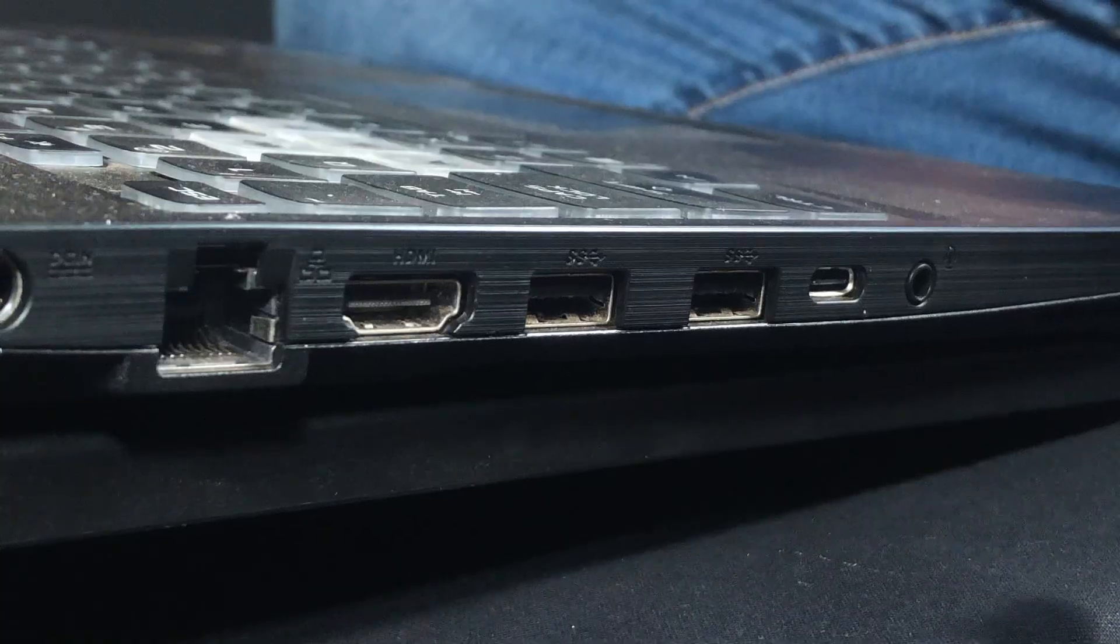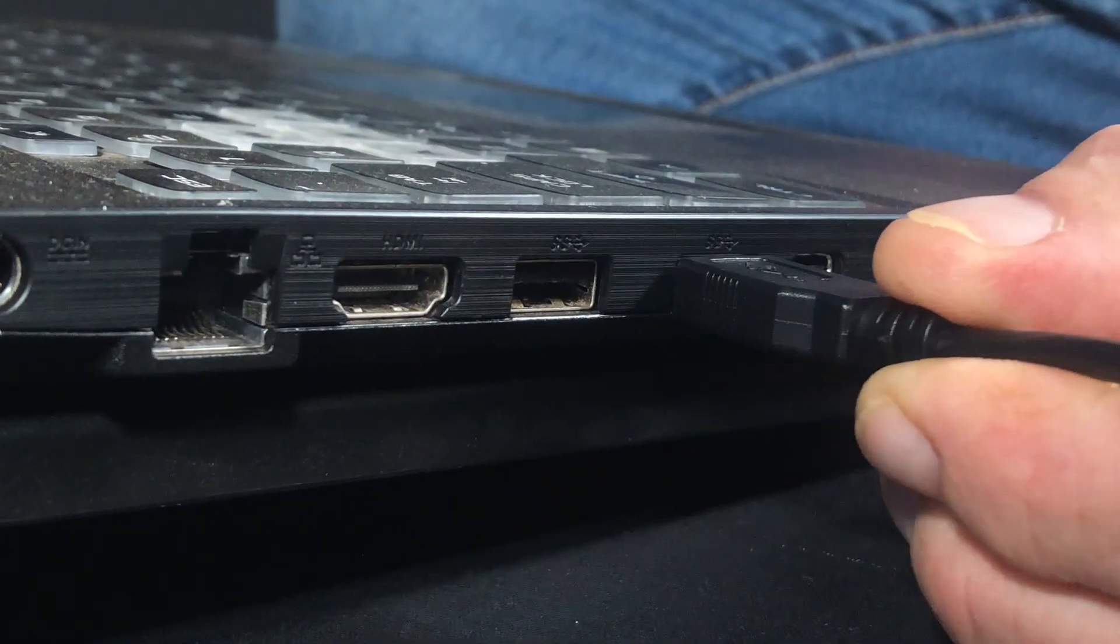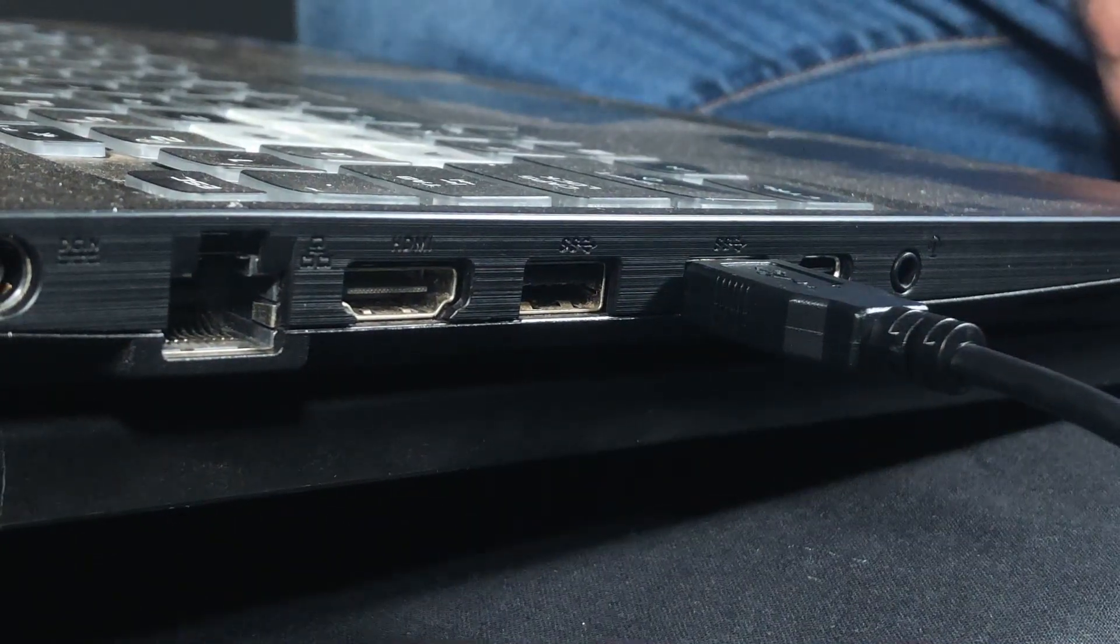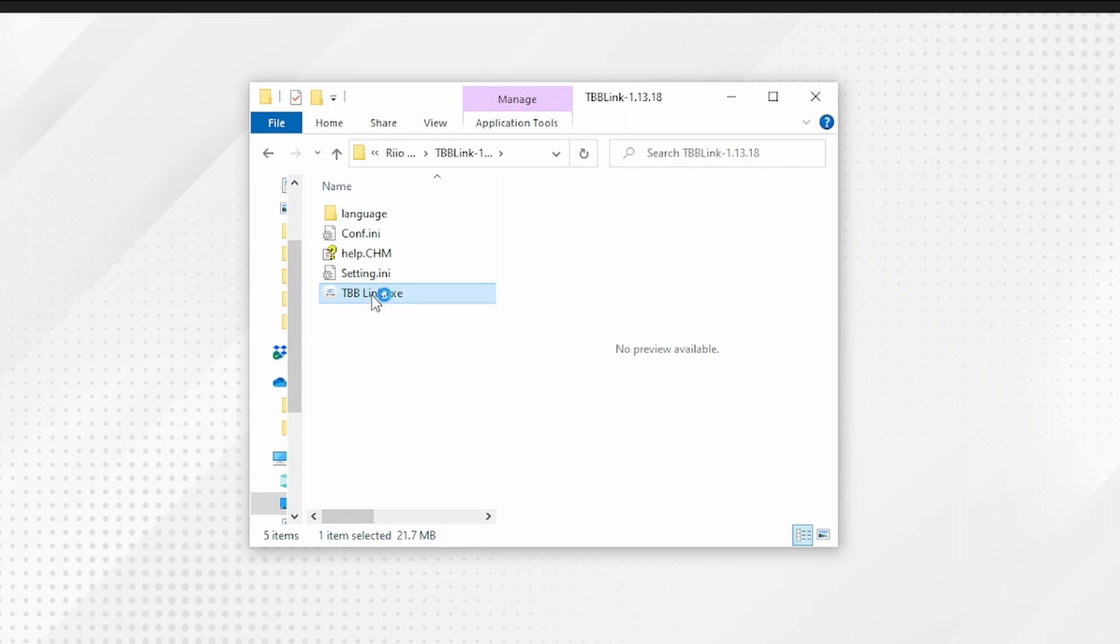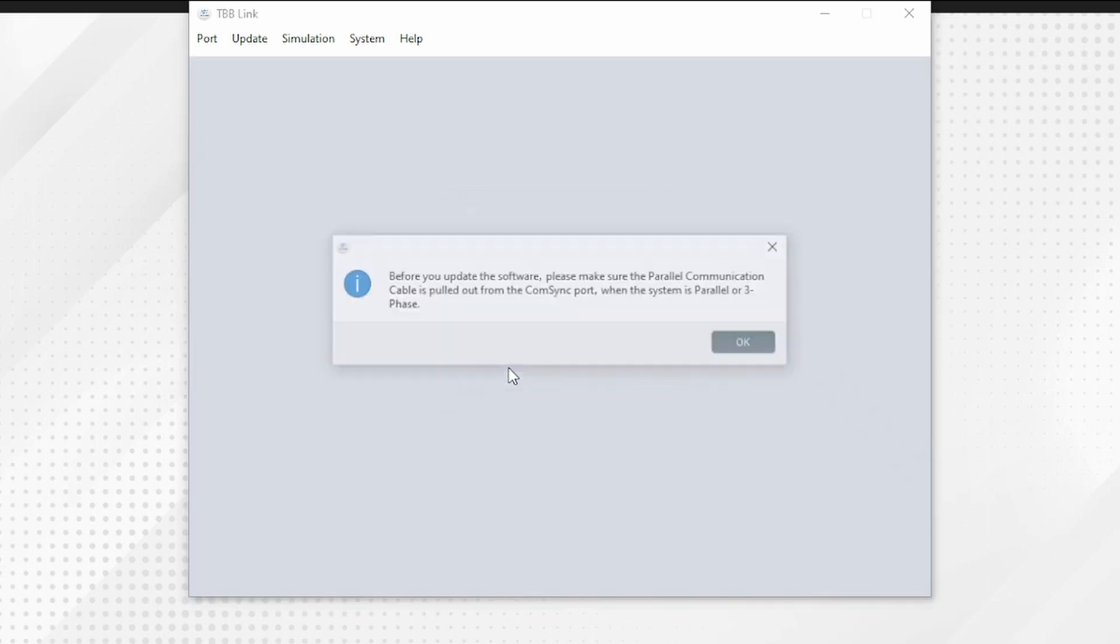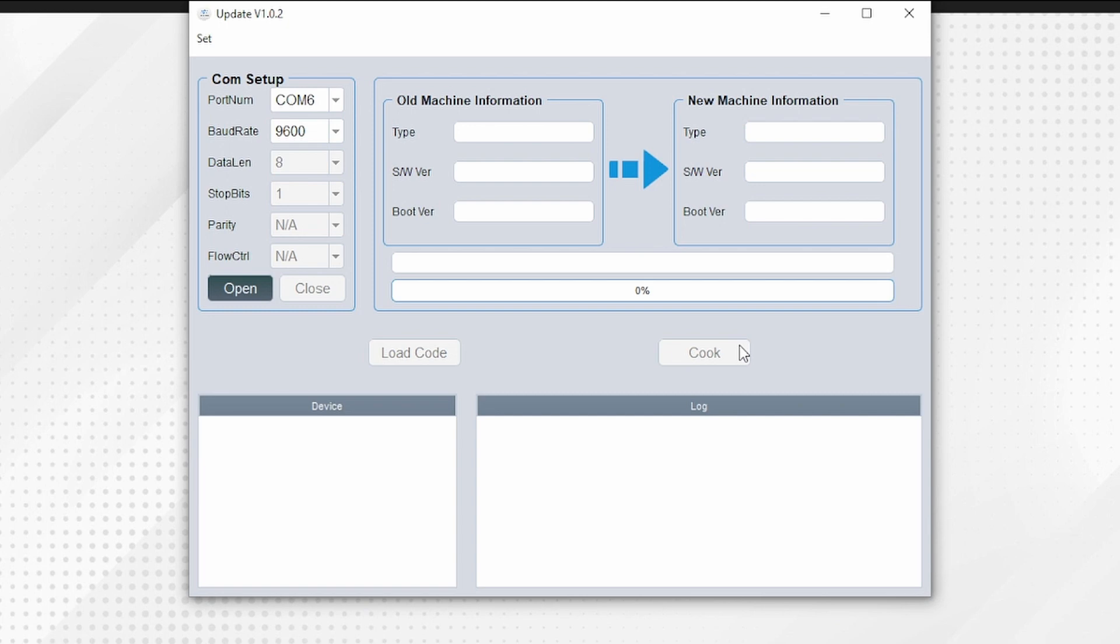Load the TBB Link software. It will ask you to select the equipment you are connected to—choose inverter. Go to the update tab and choose display software. You will need to update the display software first. A warning will be displayed asking you to make sure any parallel cables are pulled from the comm sync port when the system is in parallel or three-phase. Click OK.